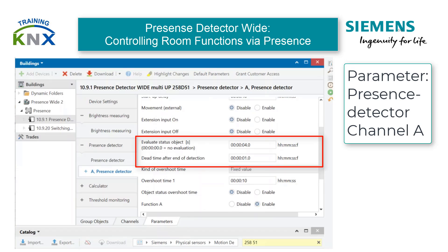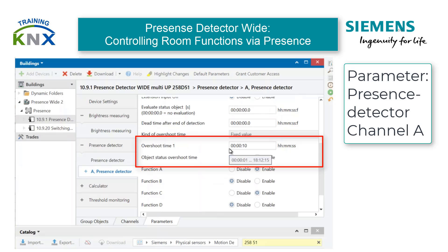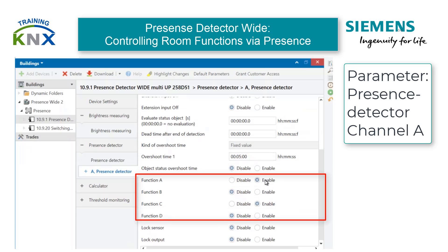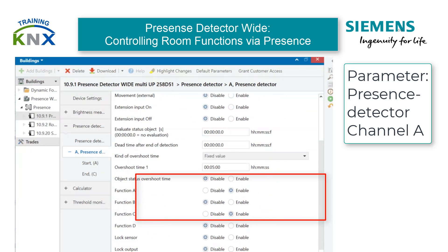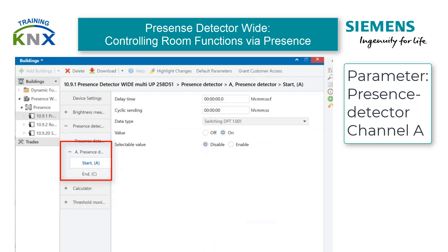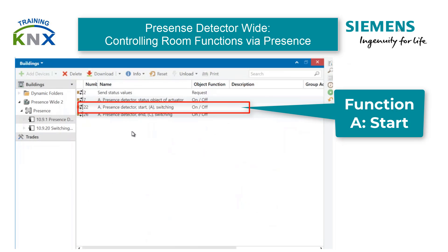Otherwise, they must be adapted to the circumstances. Next, the overshoot time 1 must be set to the desired value, here 5 minutes. This parameterization results in four functions, two of which must be used: Presence Detector Start and End Switching.